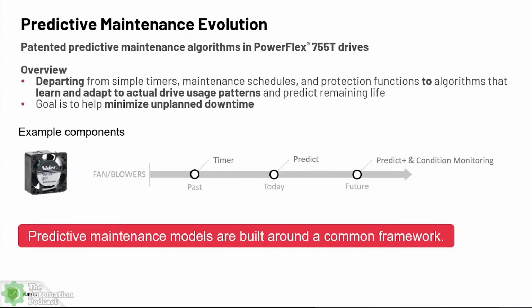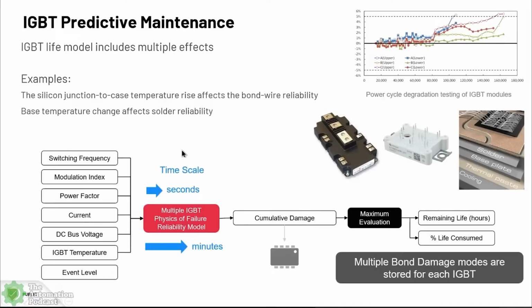But Shawn, the real question is, what about something like an IGBT? What about something like a bus cap? Two critical components to the functionality and operation of a variable frequency drive. For those who don't know what IGBTs are, that's completely understandable - this is the power device, the switching device, the silicon device that does a lot of the work inside the drive. Without an IGBT, or if that IGBT gets to the end of its life, unfortunately that means your process stops because we can no longer control your motor. So IGBTs as well as bus capacitors are critically important to the application of your VFDs. So how do we go and maintain those?